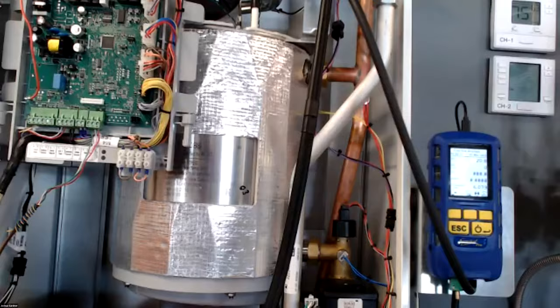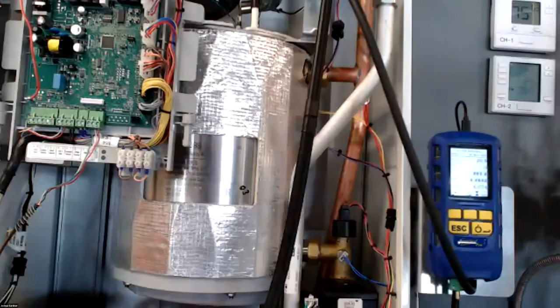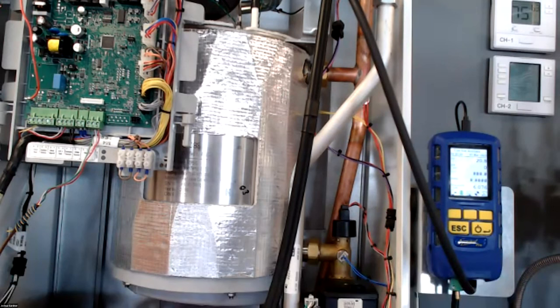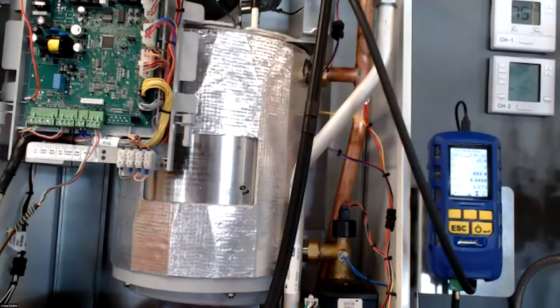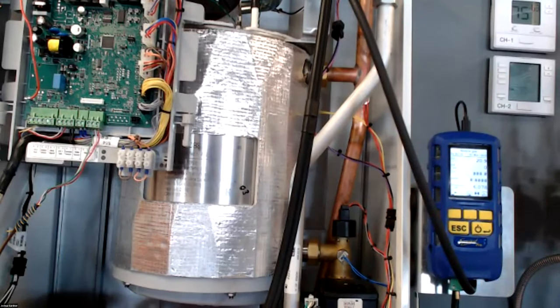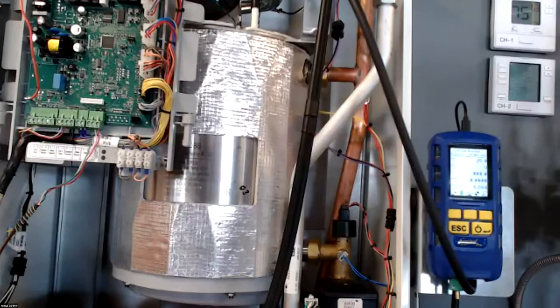And if you're able to get everything else in spec, something that some guys are seeing specifically on propane is CO being elevated and they can't get the CO down. Everything else is spot on, but they cannot get the CO level in range. Is there anything they can do to correct that in the field? The only thing I'll say is, from tech calls and job site visits where I've had that issue, it's not the setup. It's usually something to do with the venting. So my first question would be, what is the vent termination that you're using, and how does that venting install? What does it look like?